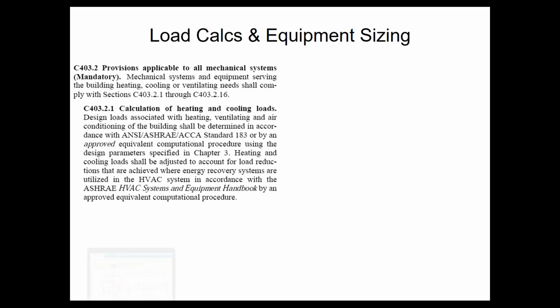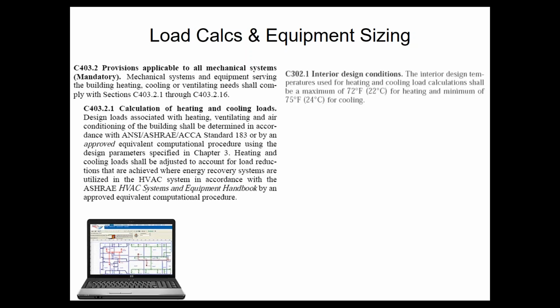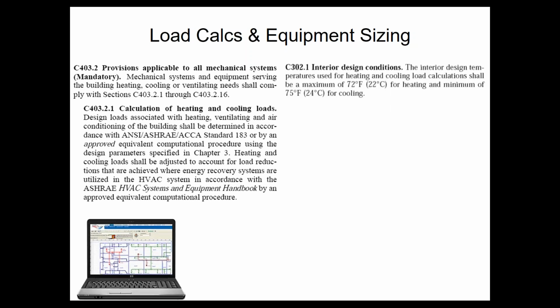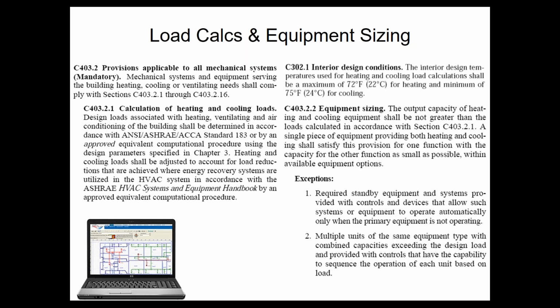All right, some of the specifics. Just like residential, on the commercial side, we have to do load calculations. You have to do them per the ASHRAE standard 183, which is not a big deal. Most of you guys know how to do that anyway. You have to use the same type of interior design temps, which means a maximum of 72 heating, a minimum of 75 cooling. That lines up. Then in regards to equipment sizing, instead of using ACCA, which is only for residential, the code spells it out here: you cannot size the system any bigger than your loads. So if your load says you need a 10-ton air conditioner, you cannot put in a 12.5. You can only put a 10. You can't even put a 10.1 in.